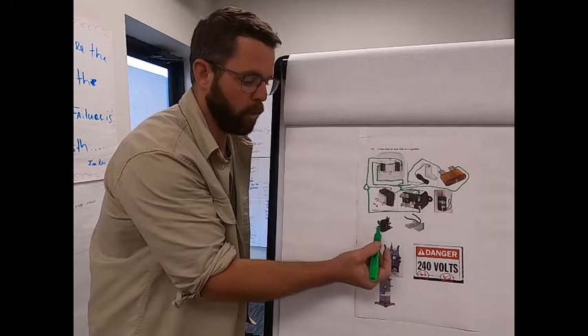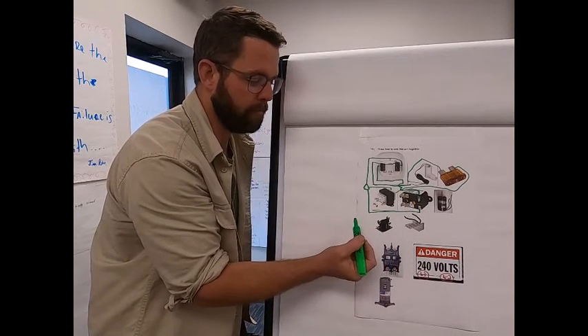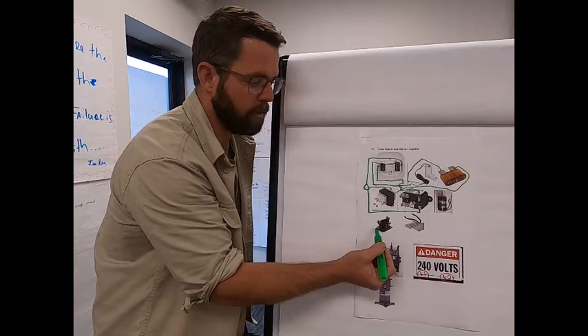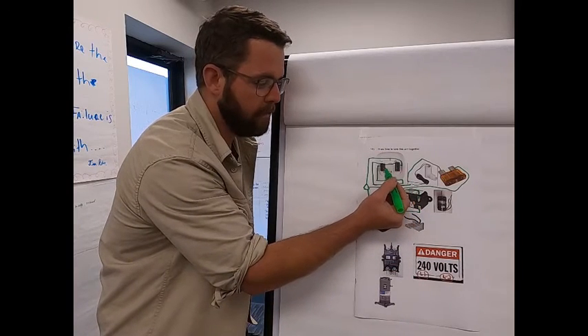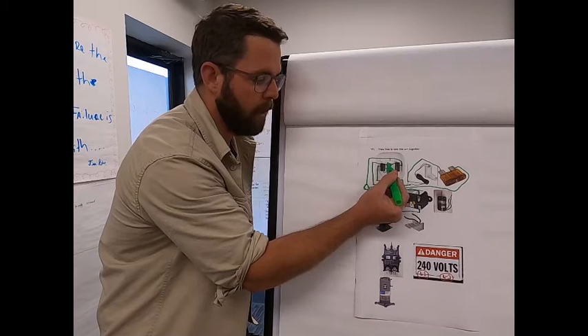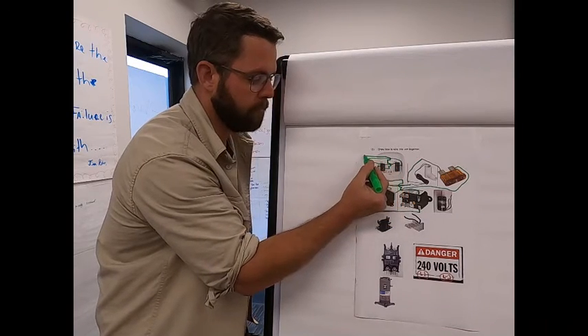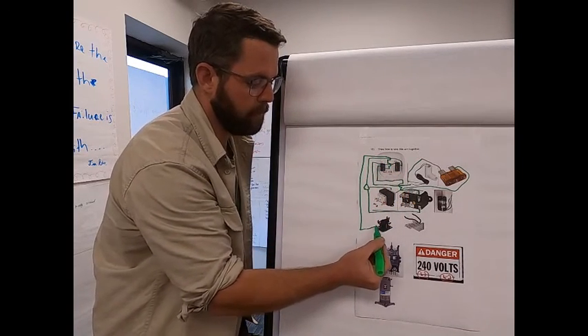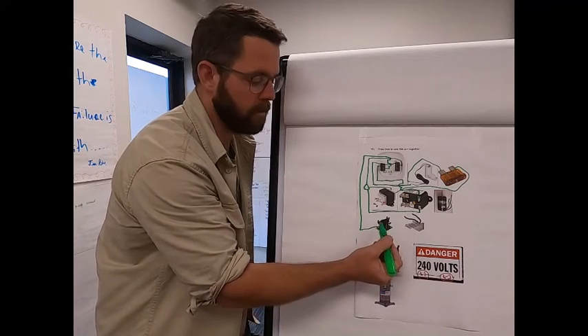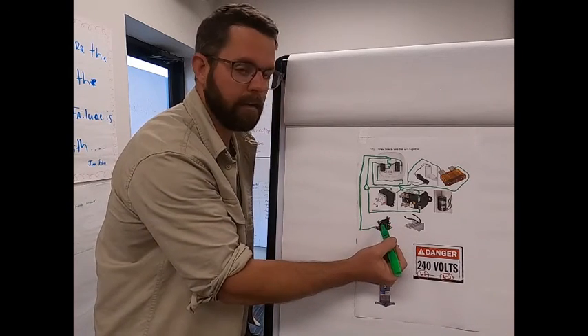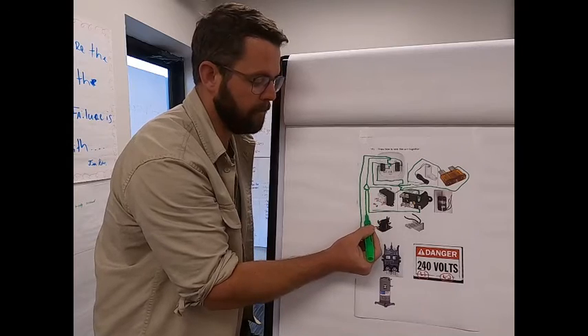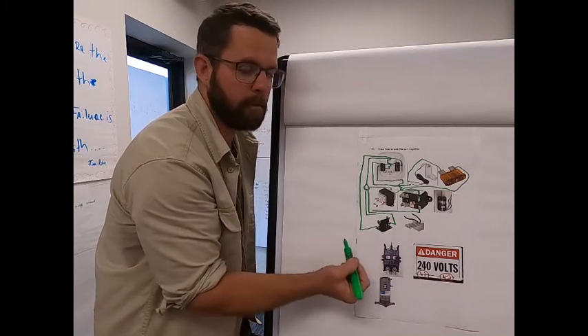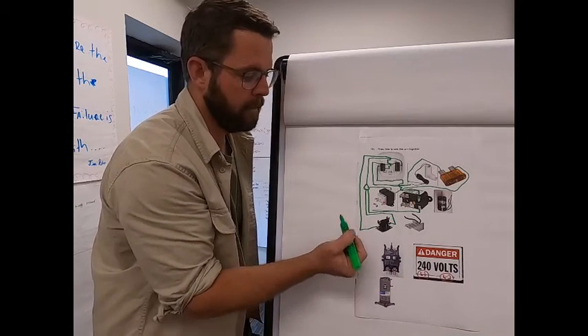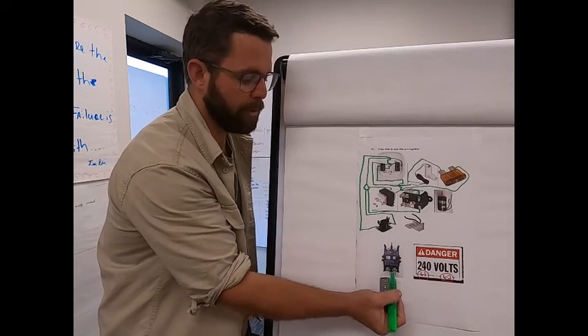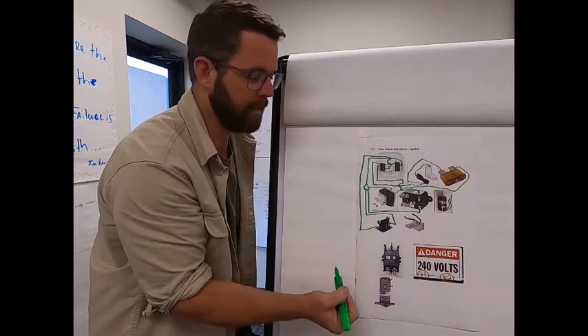Next, we're going to wire in our heat sequencer. On one side of the heat sequencer, we're going to have W1. W1 will come out of the thermostat and to the one side of the bottom of our sequencer. On the other side, you guessed it, common. Common is commonly present. Next, in our low voltage circuit, we are going to wire in our compressor contactor.